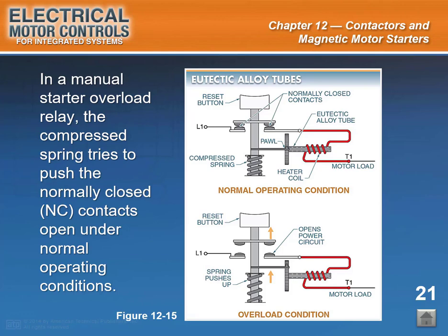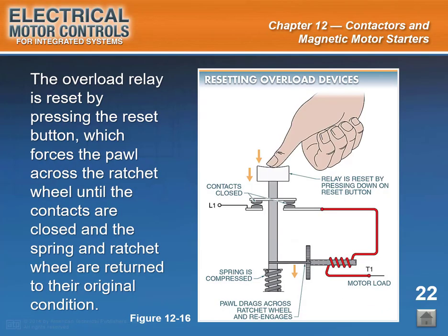The main device in an overload relay is the eutectic alloy tube. The compressed spring tries to push the normally closed overload contacts open when motor current conditions are normal. The pawl is caught in the ratchet wheel and does not let the spring push up to open the contacts. End of slide 21. Start of slide 22.